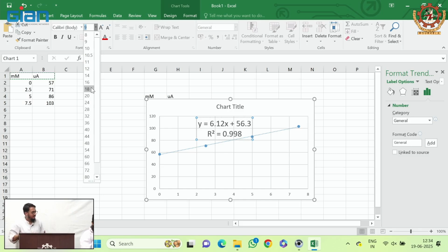So you have seen all the steps now. First step is testing or checking the working electrode. If it is fine, then you go to functionalization, where we do electropolymerization. What type of electrochemical method did we use here? Not the chemicals, the method: cyclic voltammetry. Yes, we used GOX and phenol mixed in PBS. Third, we did stabilization. The last one is calibration, which gives us the sensitivity of the sensor.